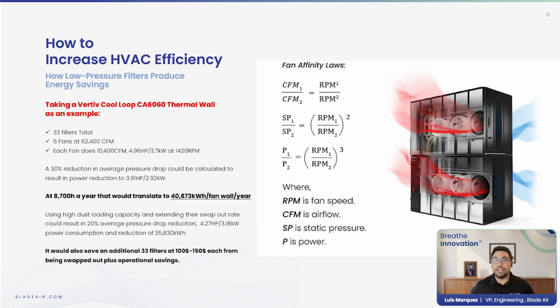This particular model has 33 filters in total. A system like this will start somewhere around 0.3 inches of water column and can go as high as up to 1 inch of water column in about 3 months, the recommended swap out rate. So we'll call it an average of 0.65.